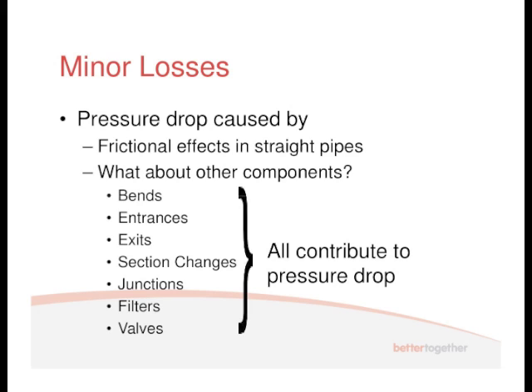The other cause for pressure losses are obviously the different components. I know in your lab you've got to work out the pressure drop across a bend in the pipe network. Well, that bend will have a certain loss factor, which we call k. And you multiply k by the dynamic pressure to work out the pressure drop across it, what the ideal pressure drop would be.